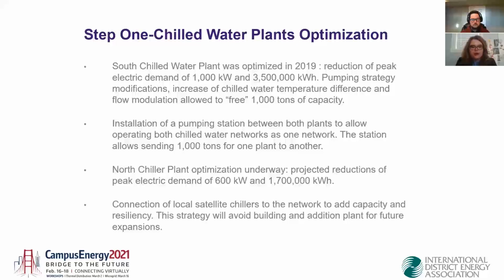And again, a pumping station was installed between both plants to allow operating the chilled water network as one network. So we take advantage of the most efficient chiller in both plants to determine which one works depending on the campus load. That transition or pumping station allowed sending 1,000 tons between one plant and the other. The North Chiller plant is underway for the optimization. The peak demand reduction is around 600 kilowatts with 1.7 million kilowatt hours of reduction.